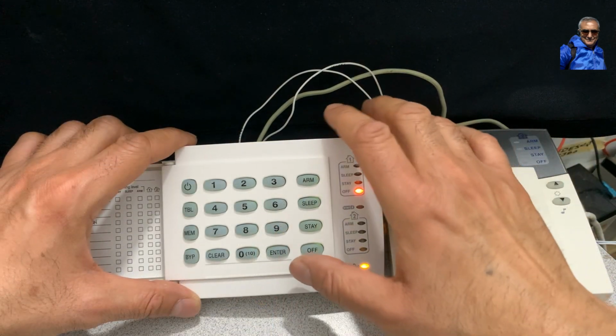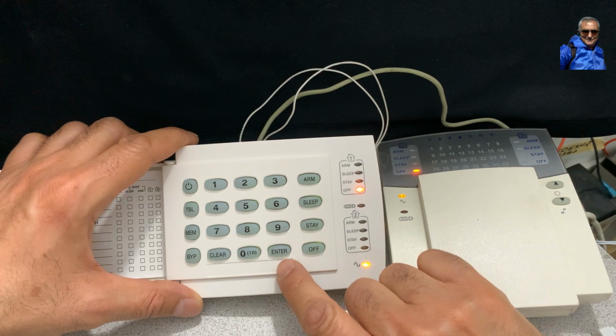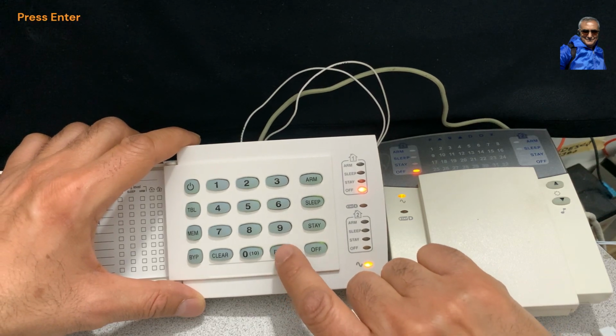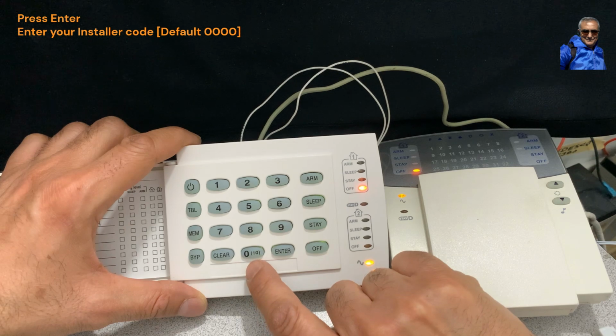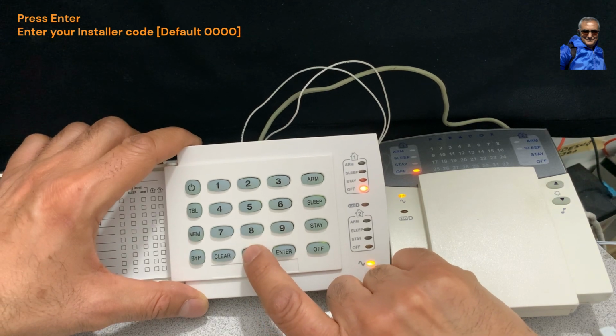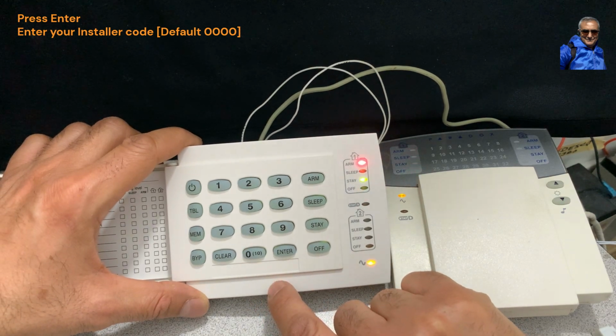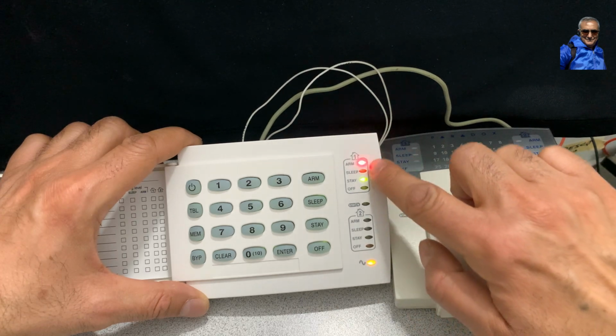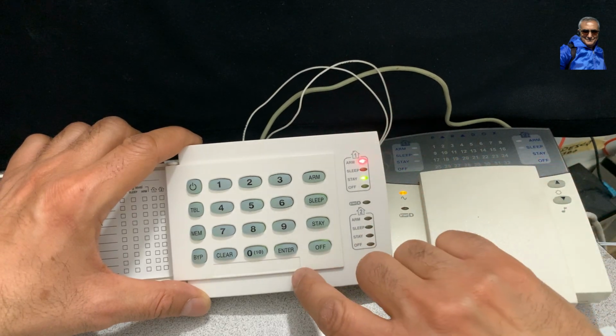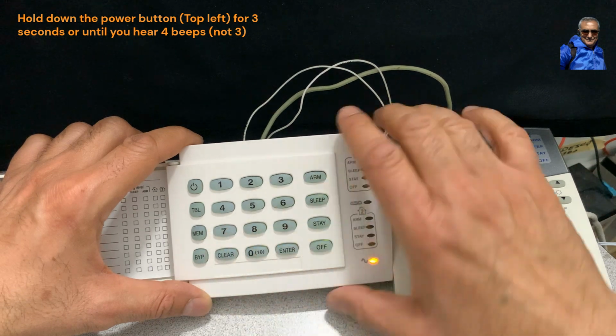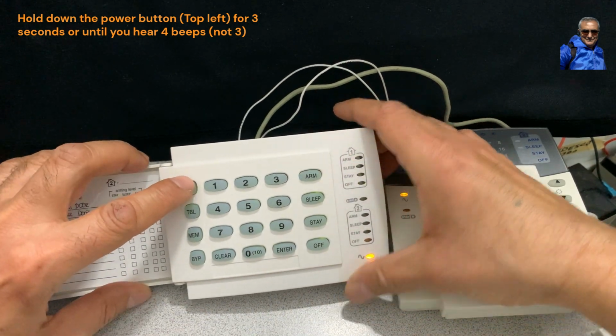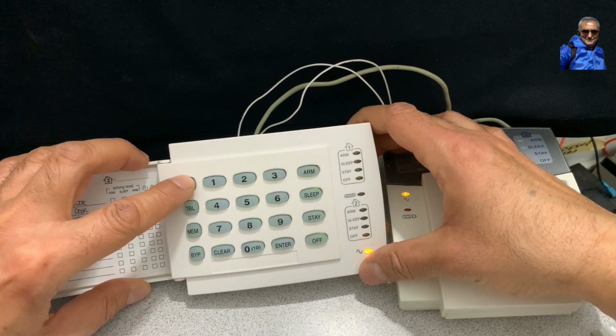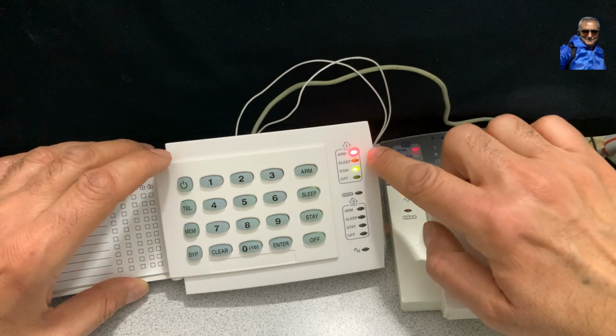Now, let's see how to do that on the K10H. Press Enter, followed by your installer code. In my case, it is 0000. Notice the arm and stay lights are blinking. Now, hold down the power button on the top left for 3 seconds or until you hear 4 beeps. Notice the arm and stay lights are solid on.